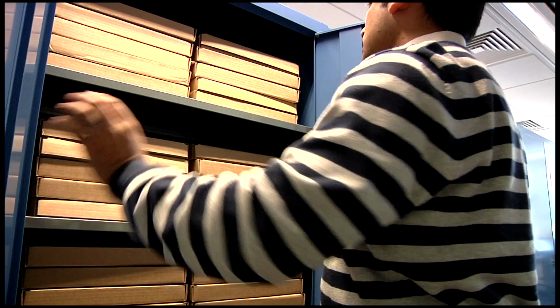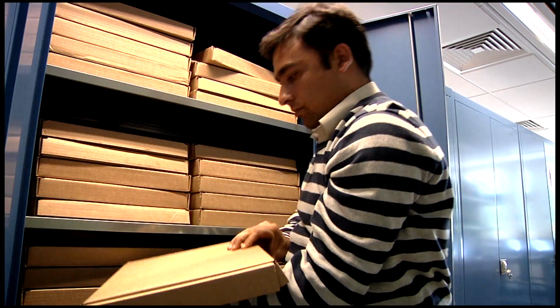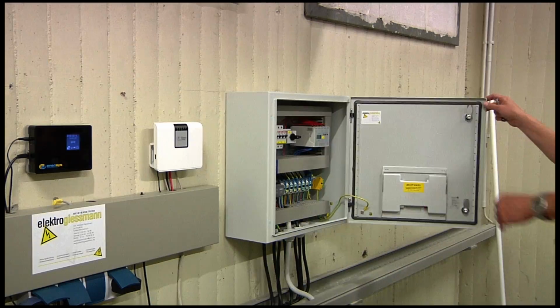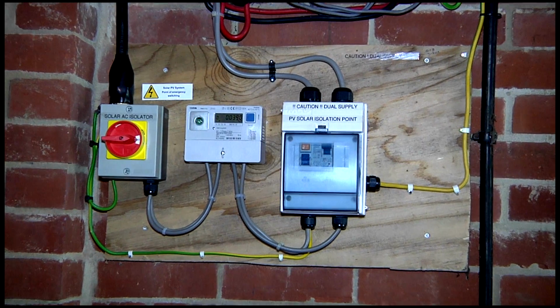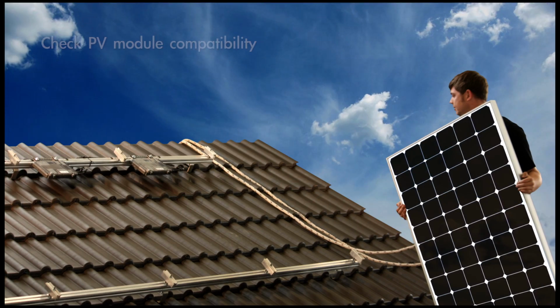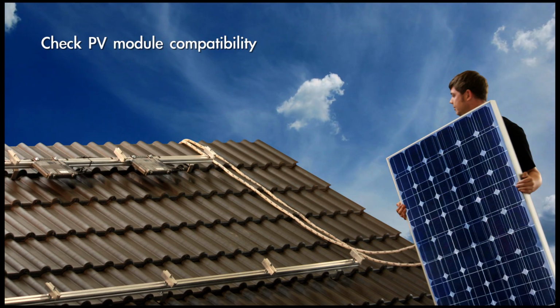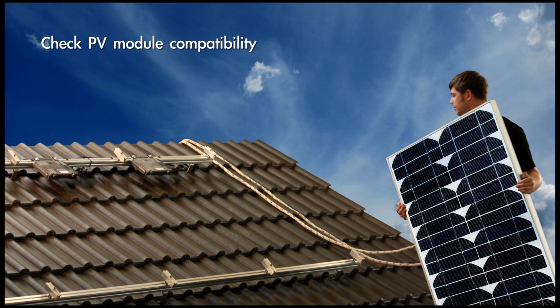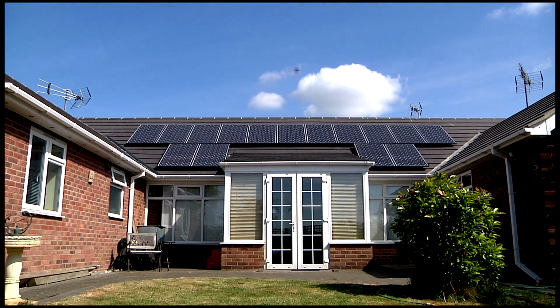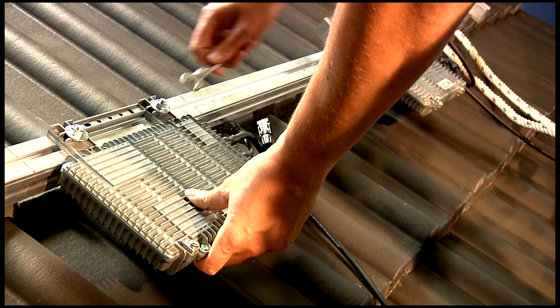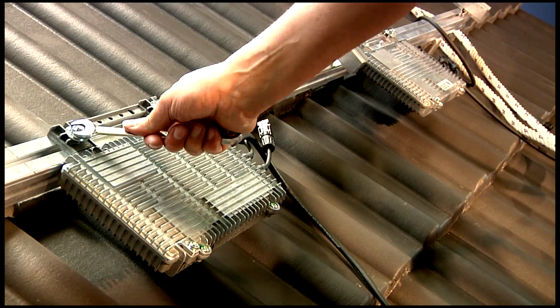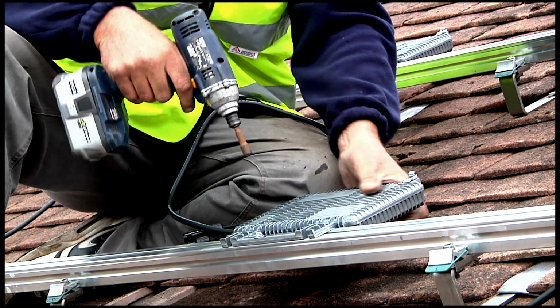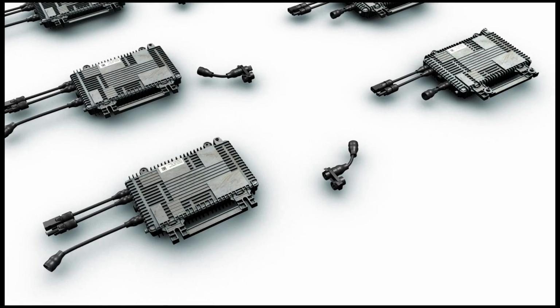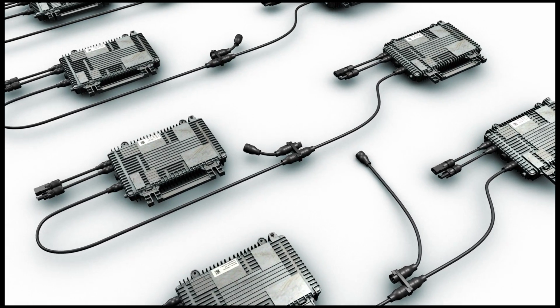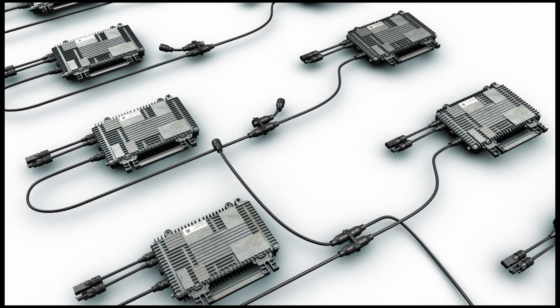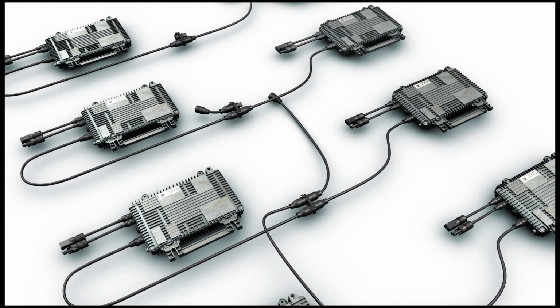Prior to installation of the microinverter system, please ensure that all storage requirements have been met. Please ensure that the installation is done in accordance with all national and local electrical codes. First, ensure that the power rating and DC voltage range of the PV modules are compatible with the microinverters. Seasonal temperature impacts on PV modules should also be considered. Enecsys microinverters can be attached to almost all PV mounting systems to fit a wide variety of applications. The number of microinverters being installed on a single AC branch circuit will depend on the applicable output current of each inverter and the maximum allowable AC current of that branch.